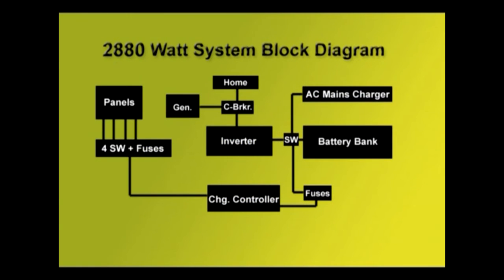If we take a look at this very full-featured system, on the top left he's got the 4 panel arrays coming in with separate wiring to 4 switches and fuses. Each one can be turned on and off so that you can isolate one panel array from the others. Then it comes down and goes right into the charge controller. After that, out of the charge controller, it goes through some fuses. Of course, circuit breakers or fuses are used here, but he's using fuses. And then into a central switch.